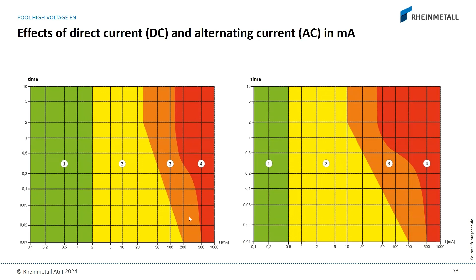You can measure this potential equalization with a 4-wire measuring device, which is a low-cost device. The only thing we need is a test current of minimum 0.2 ampere. You can buy devices with 0.1 ampere, but that's not enough to do the measurement on cars, because these tools aren't only used on cars, so we need 0.2 ampere. Also here, we can't use a multimeter for this measurement.